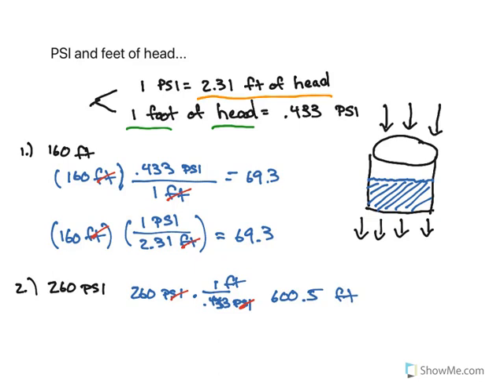Or you can do the same thing using the other conversion: 260 PSI times 2.31 feet over one PSI. Again, the PSI's cancel out. 260 times 2.31 equals, in this case, 600.6 feet of head.